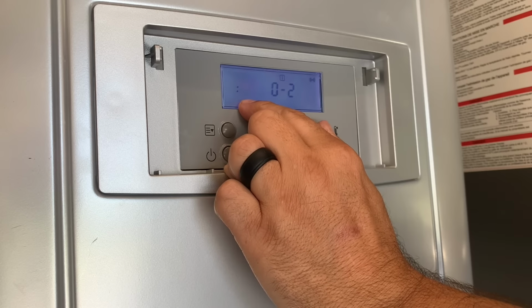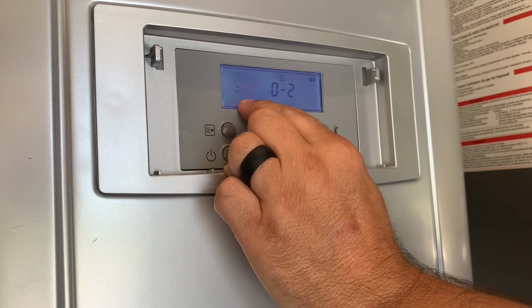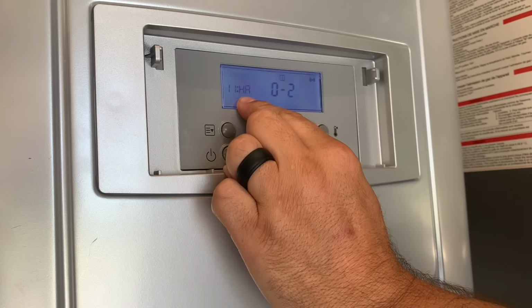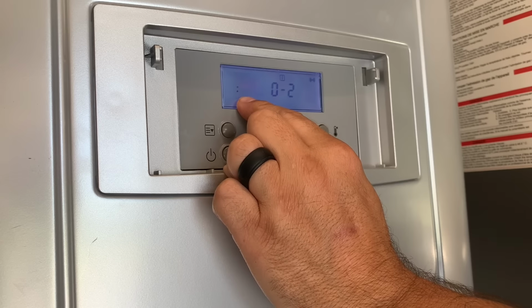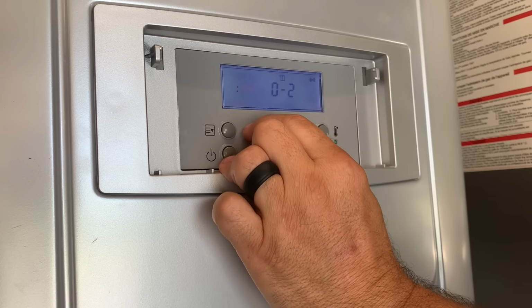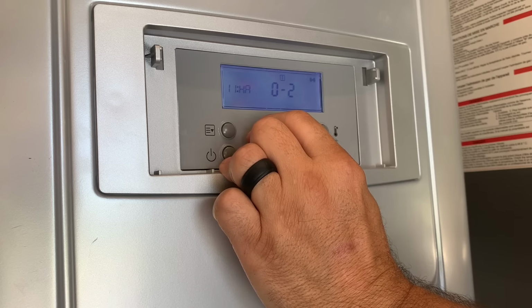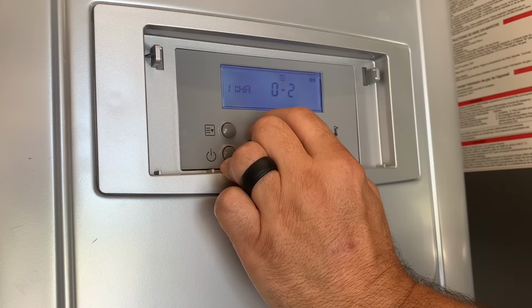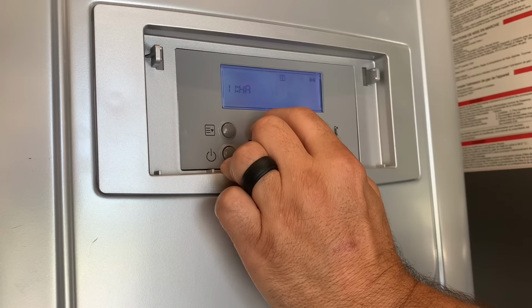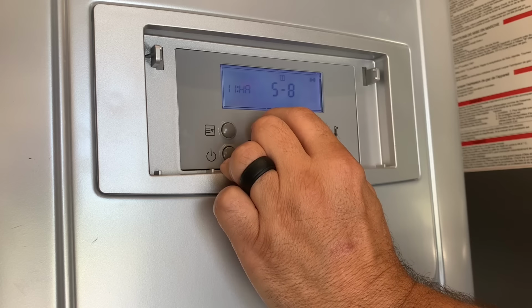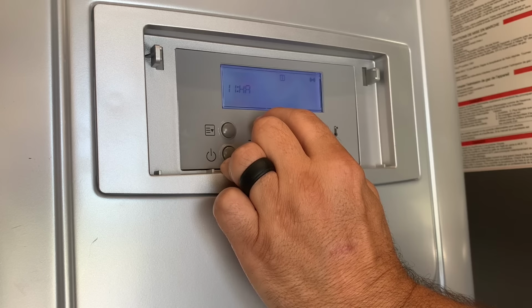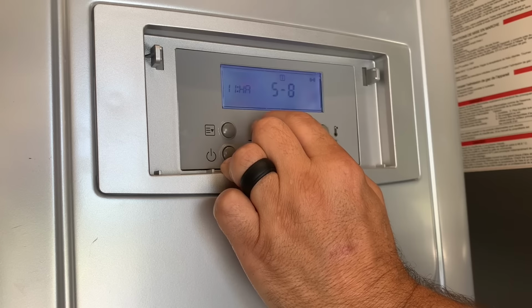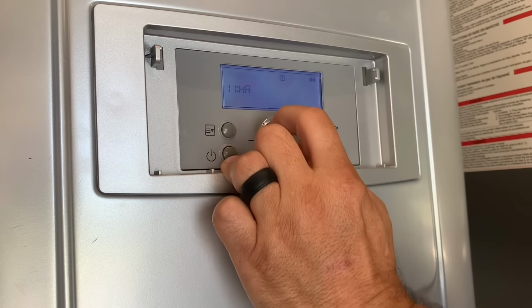1HA high elevation mode. This water heater may be installed at elevations up to 10,000 feet and operate on either natural or LP. You need to order the water heater for your particular application. Select the appropriate installation location and 02 sea level to 2,000 feet, 25, 2,000 to 5,000 feet, 58, 5,000 to 8,000 feet, 810, 8,000 to 10,000 feet. The default is going to be 02.